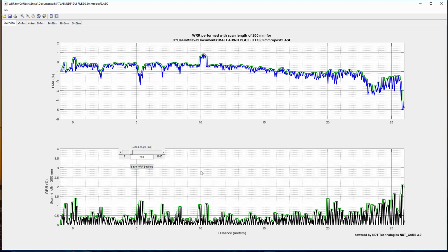this tool and the associated results with an NDT Technologies engineer. Similar to the broken wire discard criteria specified in ISO code 4309, we chose 1 and 5 lay lengths, respectively, as appropriate reference scan lengths. Note that the wire rope roughness signal shown on the y-axis is calibrated together with the LMA signal also as a percentage of rope metallic cross-sectional area, or %WRR.